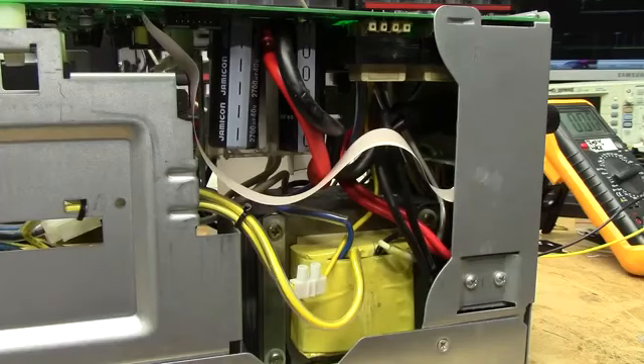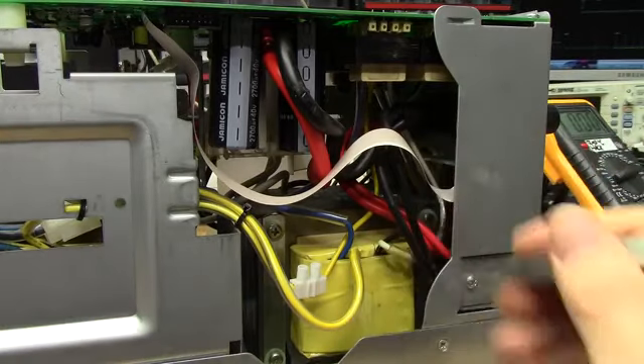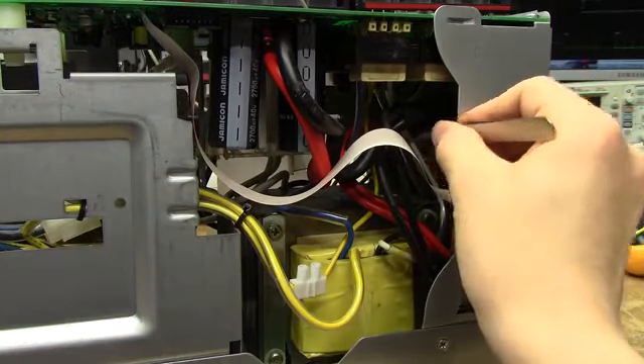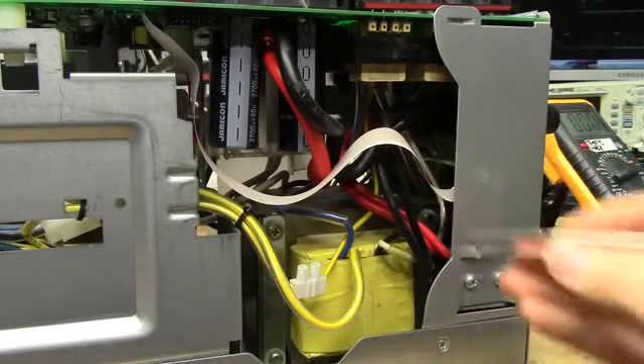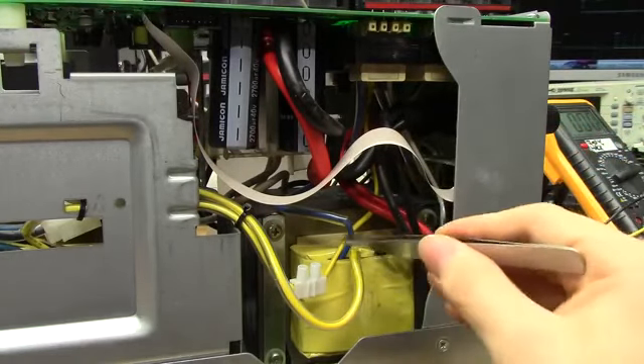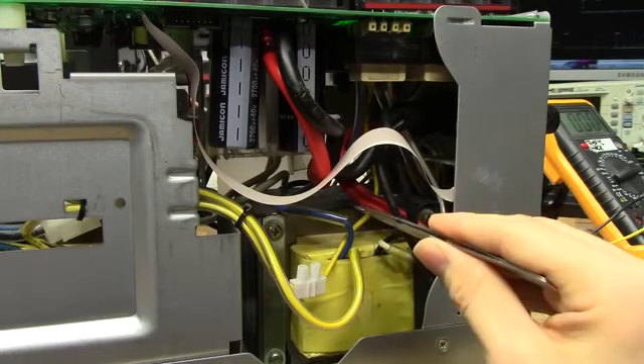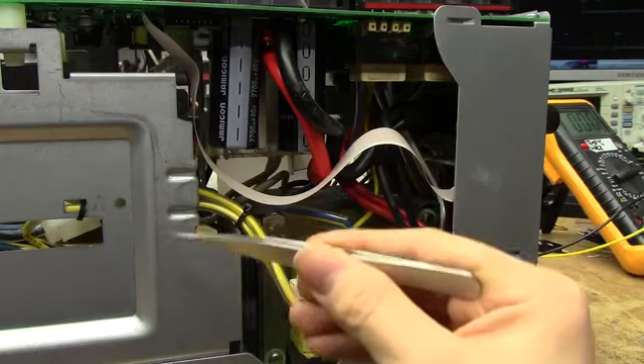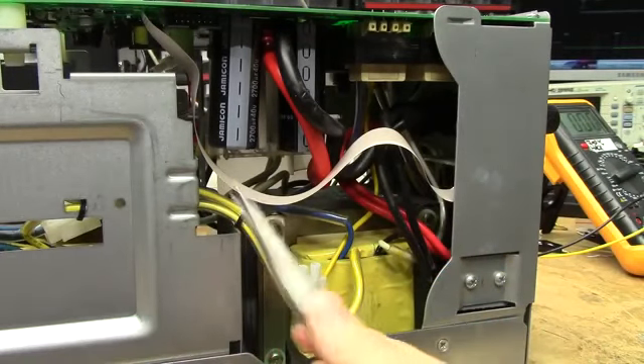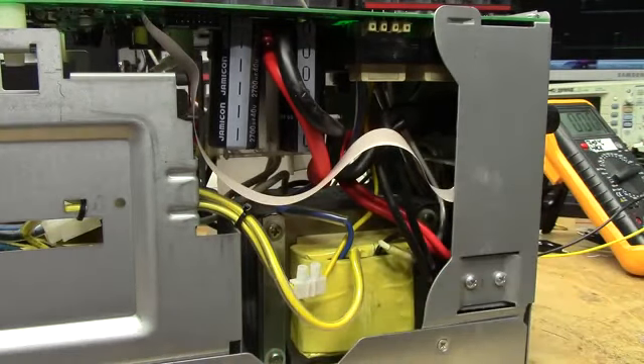The way the transformers are connected together physically is very straightforward. On the low voltage side they are obviously just connected up in parallel. But on the high voltage side, i.e. the 230 volt side, the original UPS transformer is connected entirely standard to the connector, which is in there somewhere, except for the yellow wire, which has been cut, and rather than going straight into the UPS, runs to the white wire on the new transformer, of which the yellow wire is then returning and going to the UPS. Those are the secondary windings, or the high voltage windings, and that will enable you to get the double secondary ratio on them.